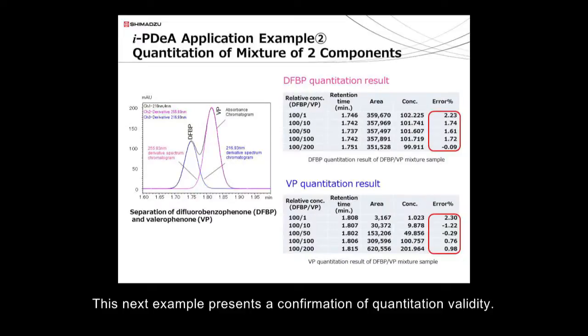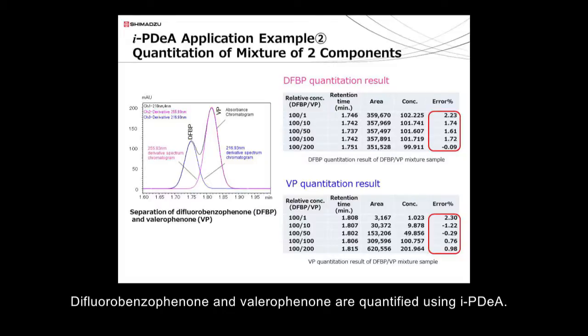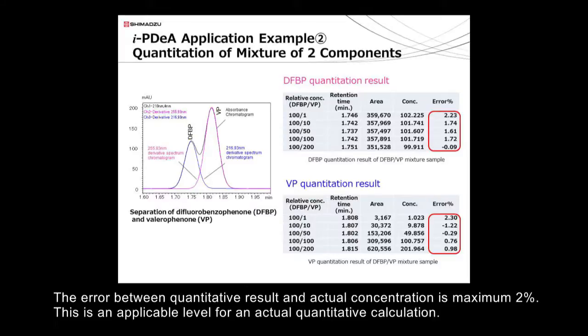This next example presents a confirmation of quantitation validity. Difluorobenzophenone and valerophenone are quantified using i-PDeA. The error between quantitative result and actual concentration is maximum 2%. This is an applicable level for an actual quantitative calculation.